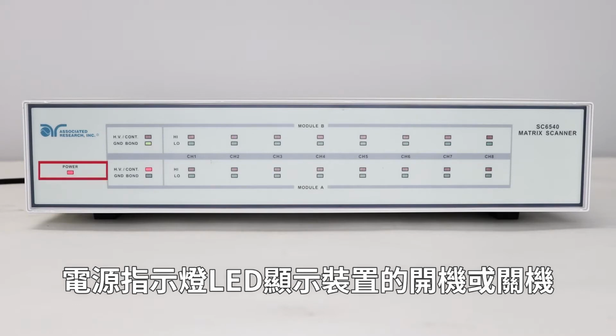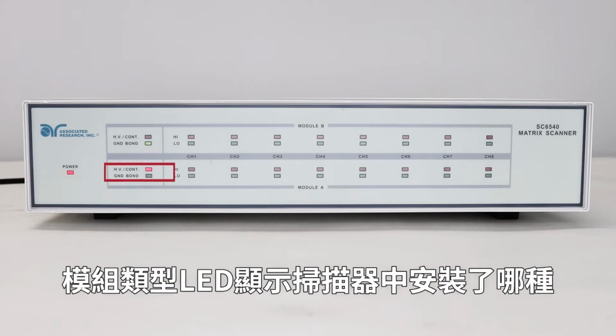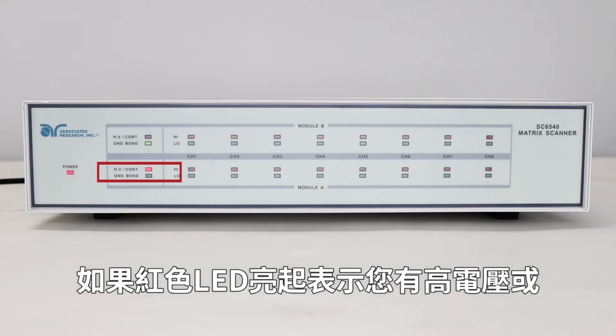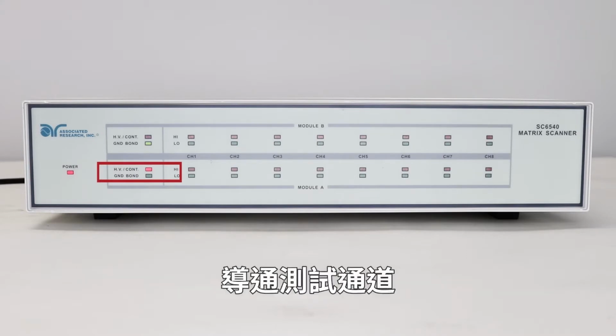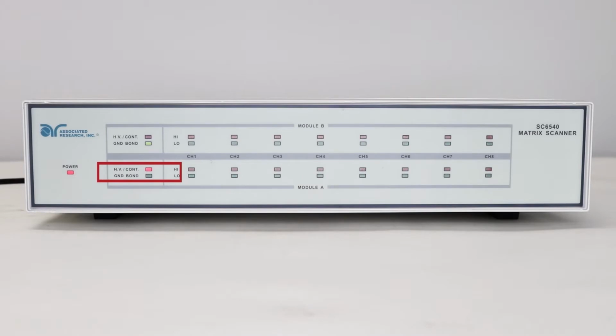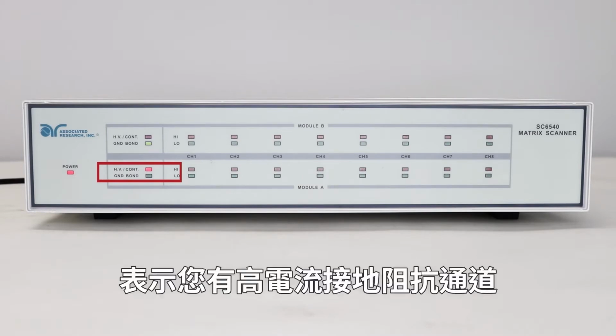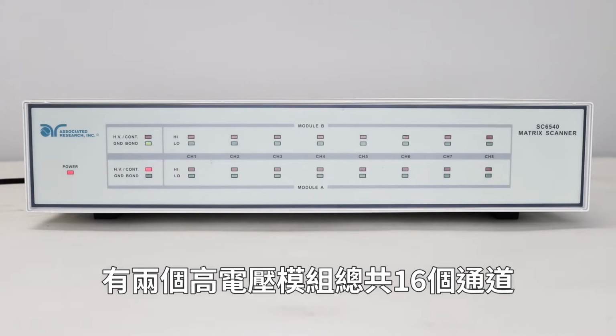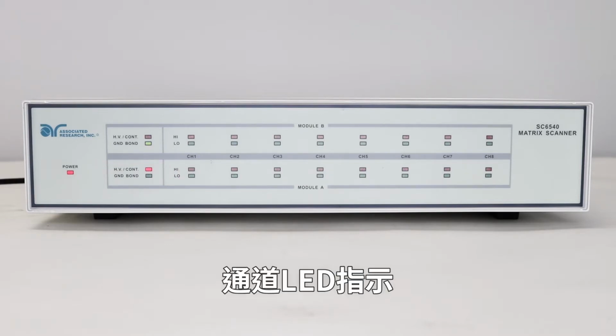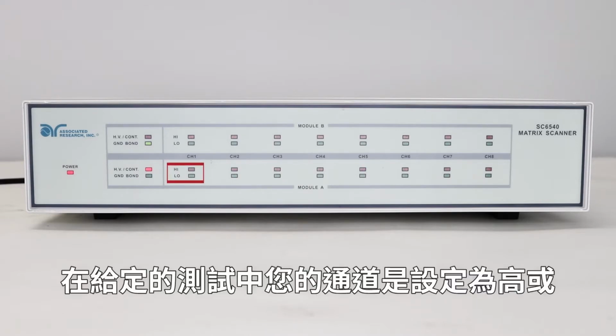The power indicator LED shows whether the unit is on or off. The module type LED shows which type of modules are installed in the scanner. If the red LED is lit, you have high voltage or continuity channels. If the green LED is lit, you have high current or ground bond channels. On this instrument, there are 2 high voltage modules for a total of 16 channels. The channel LEDs indicate whether your channel is set to high or low for the given test.